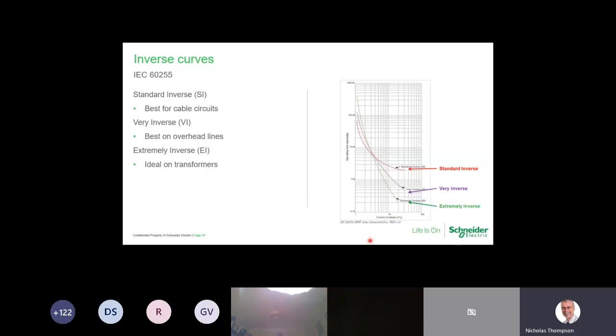But the principle here is, depending on which curve you're going to have, and I'll just do a very simple drawing using my pen. So if we take this example here, and it's a very, very straight line there. If we take the inverse curve, the standard inverse curve, that's going to have quite a lengthy tripping time. If we move to the next curve, the very inverse curve, we've got a shorter tripping time, and with the extremely inverse curve, we've got a very, very quick tripping time. So it's how the curves are used, depending on the characteristics of the network and how we're trying to coordinate various different circuit breakers together. Now, and again, I'll reiterate this, it's not for me to determine which curve is going to be appropriate for which application.